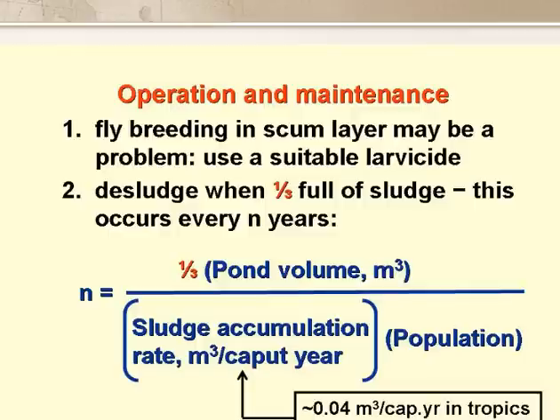There are two special O&M requirements for anaerobic ponds. Firstly, you may need to spray the scum layer with a biodegradable larvicide if fly breeding becomes a nuisance. And secondly, the ponds need to be desludged regularly — they should never be allowed to be more than half full of sludge, and ideally not more than a third full. An anaerobic pond becomes a third full of sludge after N years, where N equals one third of the pond volume in cubic metres, divided by the sludge accumulation rate in cubic metres per person per year, and the population served. The sludge accumulation rate is about 0.04 m³ per person per year in the tropics, and about two to three times that value in temperate climates.